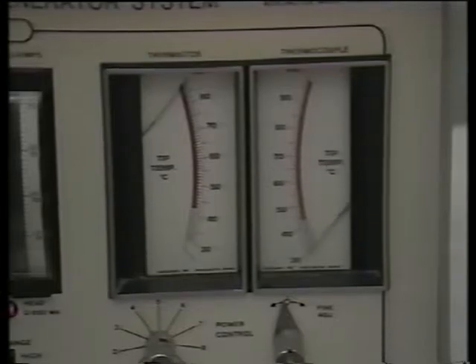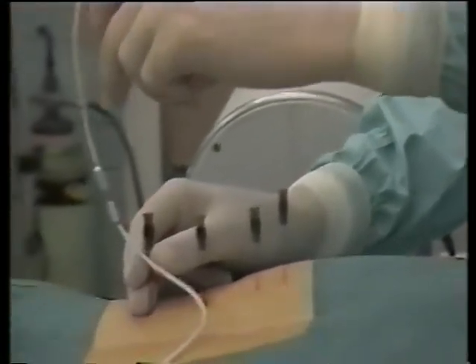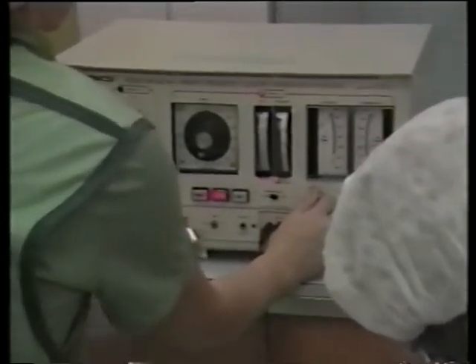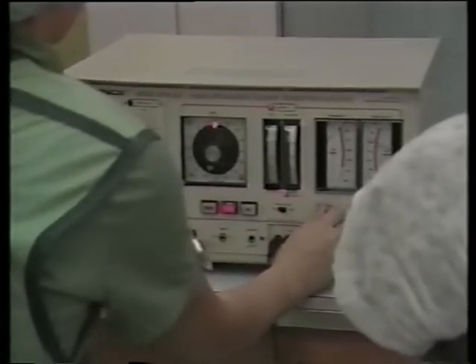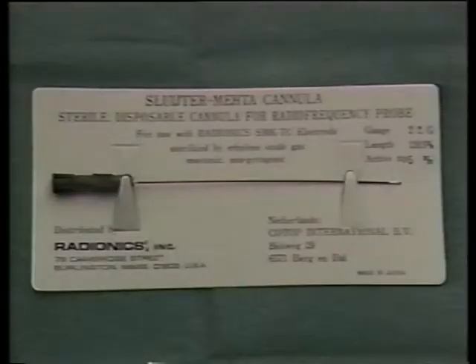The temperature at the tip of the electrode can be measured with a thermistor or with a thermocouple. The more advanced type of monitoring is with a thermocouple, since these probes can be made of a very fine diameter. Therefore, they can be used in conjunction with small diameter cannulae. This enables the operator to introduce a cannula without prior administration of local anesthetic solution into the deeper layers. We can therefore make full use of electrostimulation. For the lumbar facet denervation, we use disposable 22-gauge SMK cannulae. They come in 6, 10, or 15 centimeter lengths. Usually the 10 centimeter variety is adequate for a facet denervation. These cannulae are Teflon covered except for a 5 millimeter active tip. When the stylet is removed, they accommodate the RF probe of corresponding length.